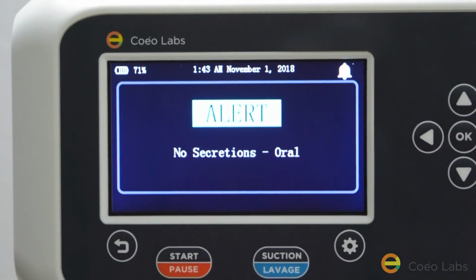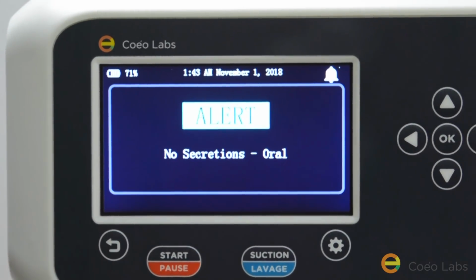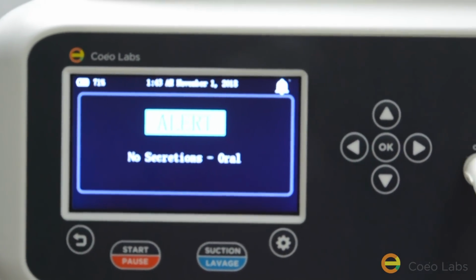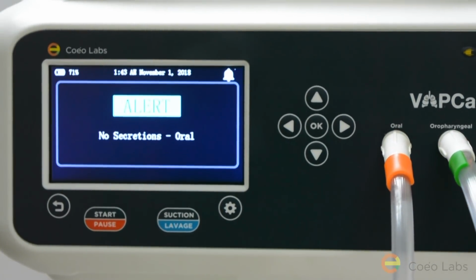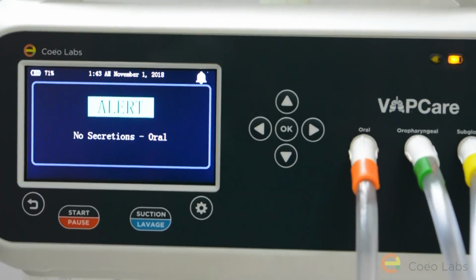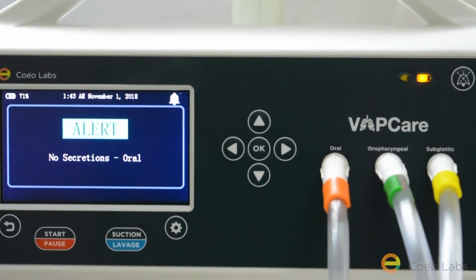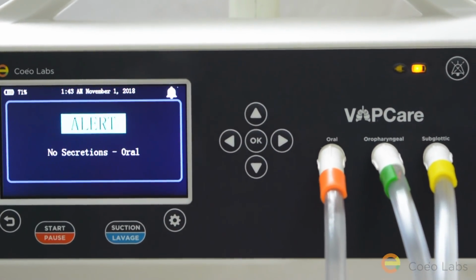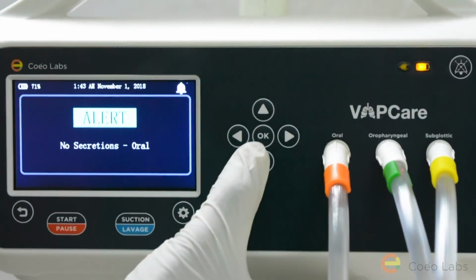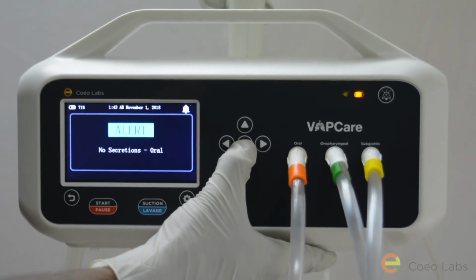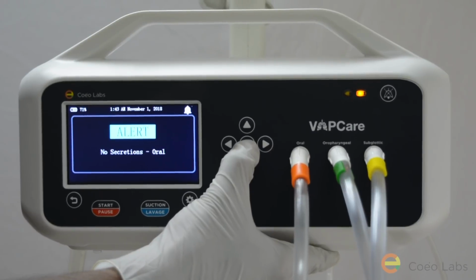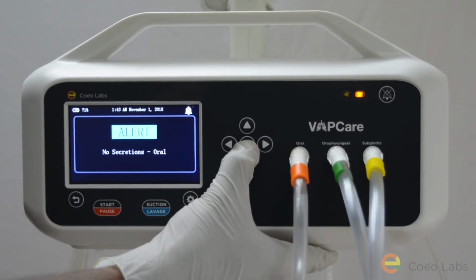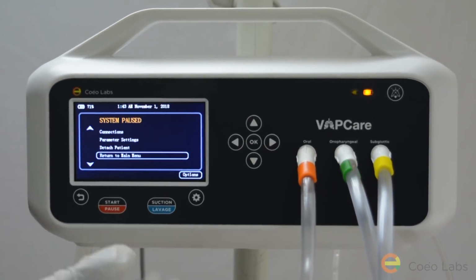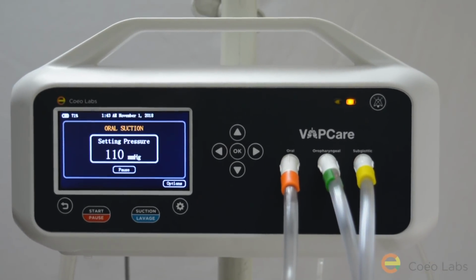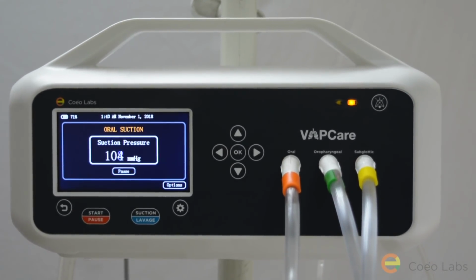If the device detects an absence of secretions in any specific anatomical region for 3 consecutive cycles, the device throws a no secretion alert. This alert will stay on the screen for the period of 5 minutes till any health staff is going to attend and then press OK. Else, the device is going to resume its function after 5 minutes. I am pressing OK here. So the device will start resuming its function. So now it is doing its oral suction again.